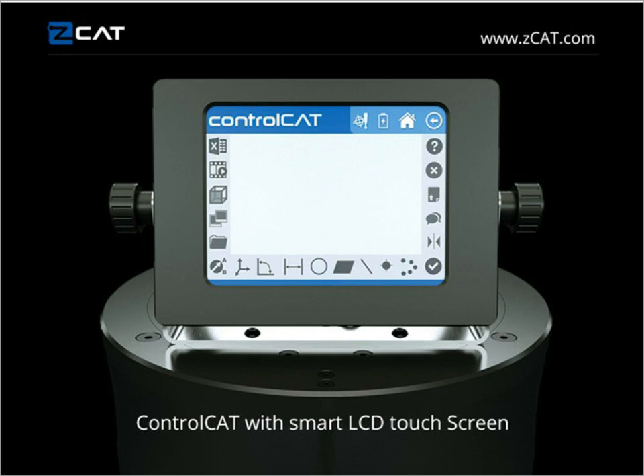I'll show you a brief video in a second, but I wanted to talk about how we can completely program the zCAT from this screen, including the speed that the probe is going to move to a maximum of 150 millimeters per second. We can program the approach distance. We can program the measuring speed while it's taking a measurement. You'll see from the screen here, it has a few other icons, a home, a battery indicator telling you how the battery life is, and we can also print out from this screen. We can do quite a few things.